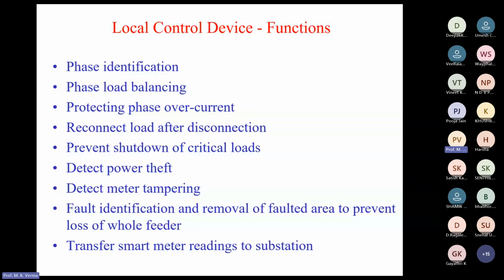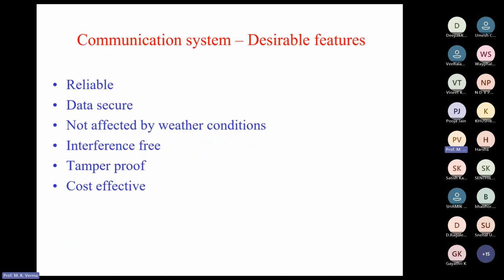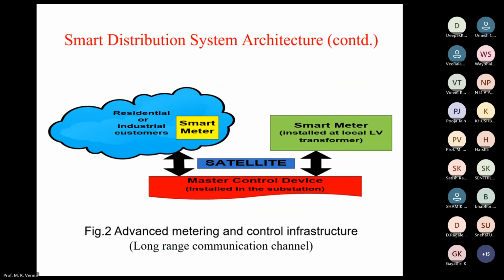So for control, we have two controllers. One is a local controller, which I have shown here along with the smart meter. The local controller may be put at a distribution transformer, and the master controller can be put at the main substation.